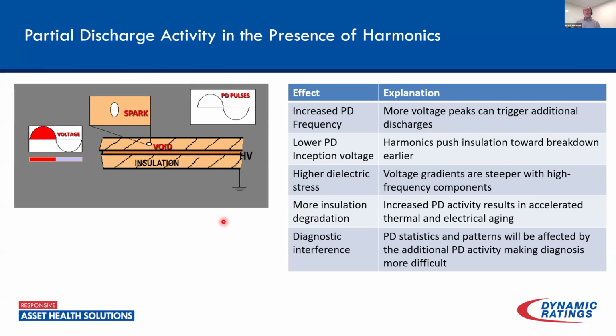So the next part: we talked about partial discharge and the impact it can have on the insulation. Of course, partial discharge is one of the leading causes of insulation breakdown. Typically, true partial discharge, if I'm looking at a void in the insulation, occurs as the voltage stress is increasing on the sine wave. So it's between 0 and 45 degrees here, and from 180 to 225 here. After that, the pulses are going to start to decrease. They tend to be at a minimum at 90, or extinguished at that point. So as that voltage stress is increasing, that's when we're seeing that insulation spark over. The reason is that the void in the insulation has a lower dielectric strength than the insulation surrounding it.